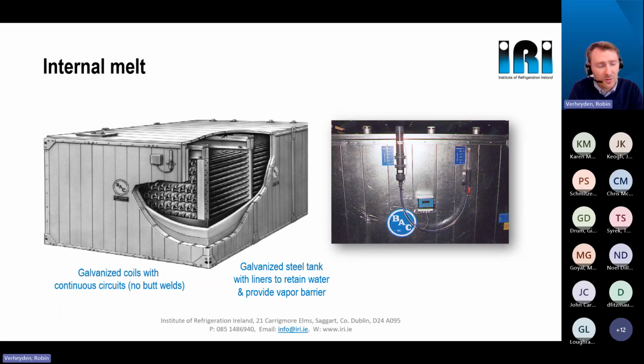And to measure the amount of ice, we use our sensor on the ice tank. This sensor uses the difference in density of water and ice. By changing from water to ice, you will see that the level of water in the tank will change because the density changed.